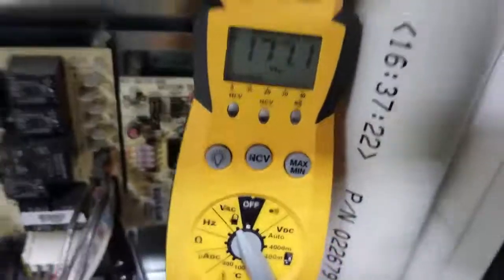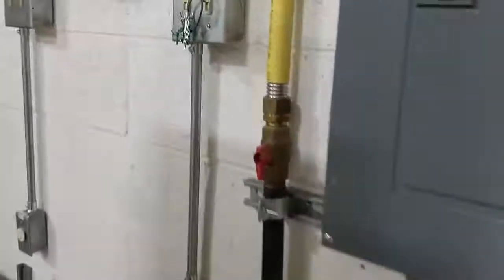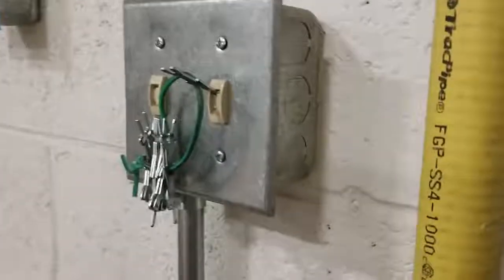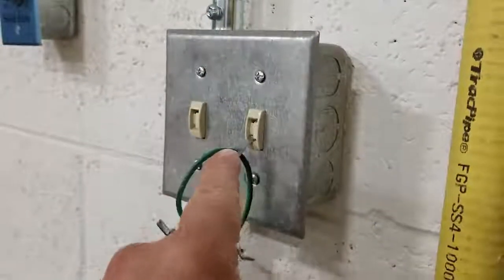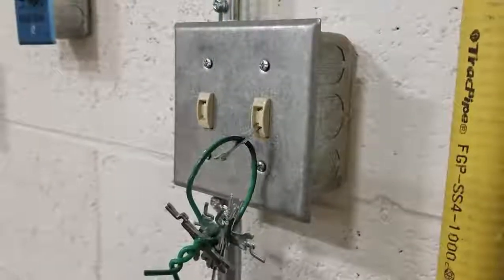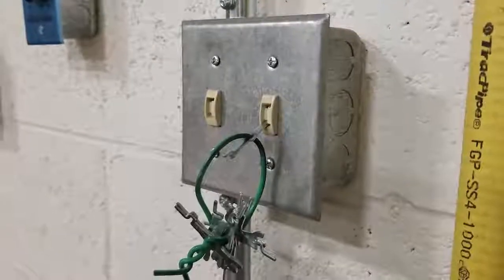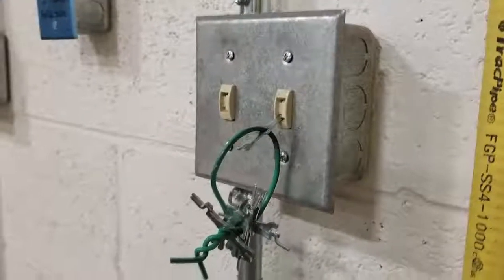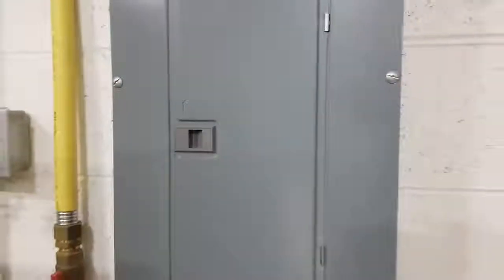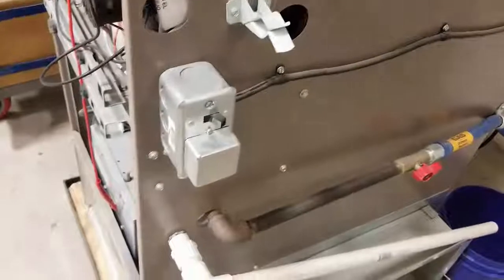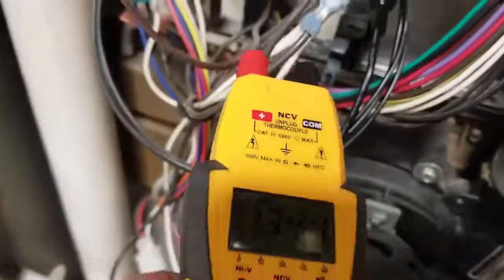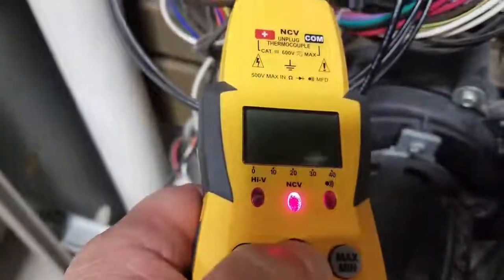Okay, now I have the ability on this system to manipulate the neutral side. So with this switch I can simulate either a broken, disconnected, or a loose neutral wire somewhere in the circuit. It could be in a junction box, it could be in an electrical panel, it could be in a disconnect box at the furnace, but basically what we've done is we've eliminated the neutral. The problem with non-contact voltmeters is even though the circuit's not complete, there's no neutral, this still tells me there's voltage.